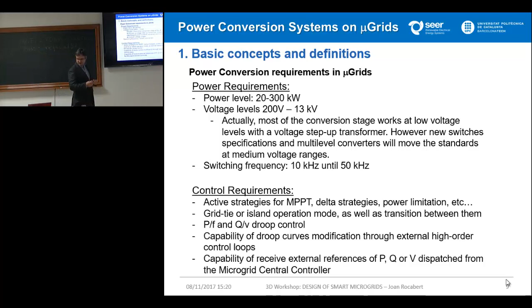Which are the roles of the microgrid power converters? Mainly there are three roles. Okay? The grid feeding, the grid supporting, and the grid forming one. Mainly the grid feeding ones are the most standard, or at least the most implemented. Okay? Because it's basic, mainly the MPPT algorithm. Okay, it's a matter of injecting as much power as I am able to.